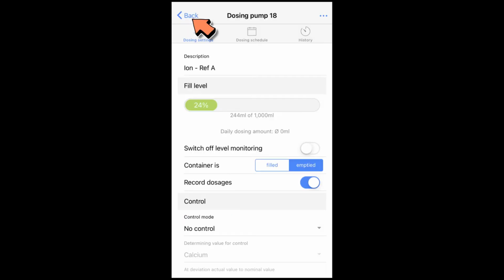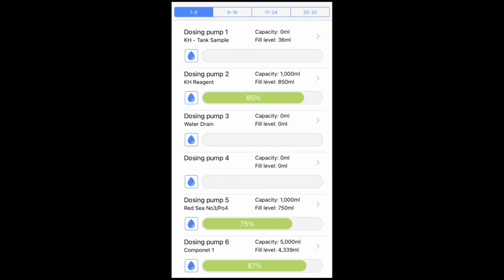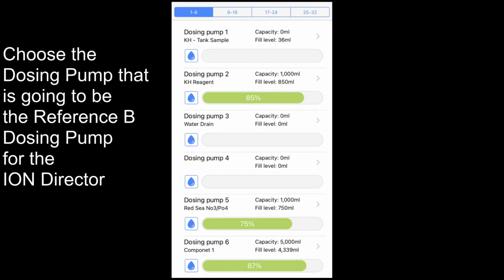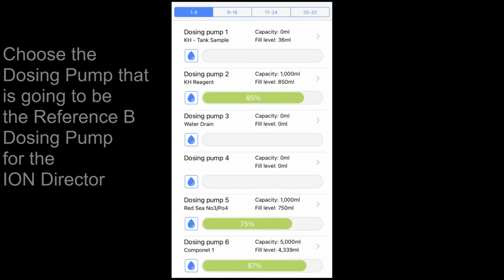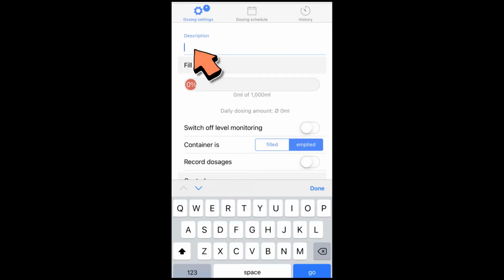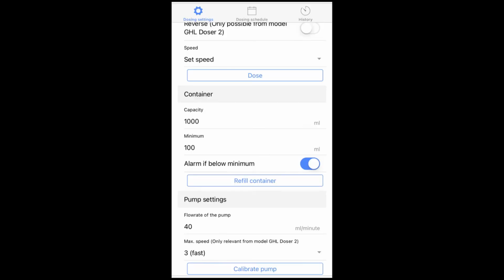Click back on the upper left-hand corner of the screen and choose the dosing pump that will be supplying the reference B solution to the ion director. For me, this is pump 19. Enter in a description that you wish to use for the dosing pump. For me, I entered in ion reference B. Scroll down to the container and enter in a capacity of 500 or 1,000, depending again on the amount of reference solution that you're using. Then enter in a minimum value. For me, I entered in 100.